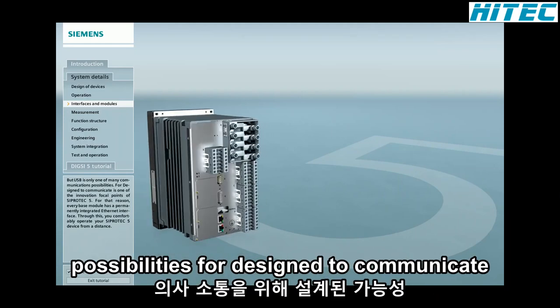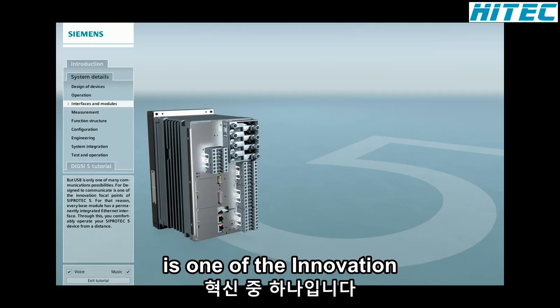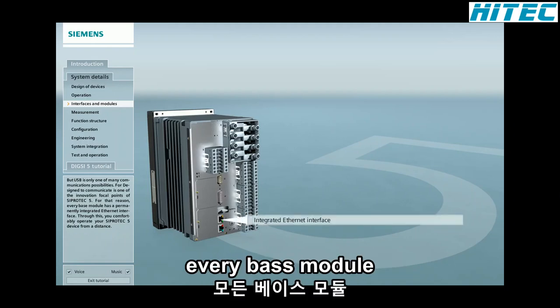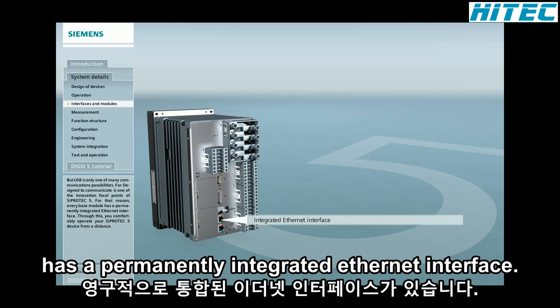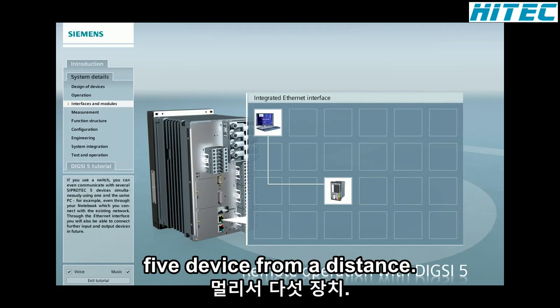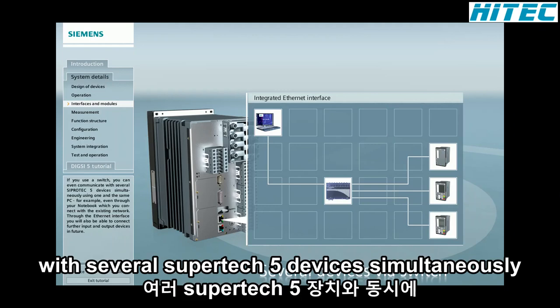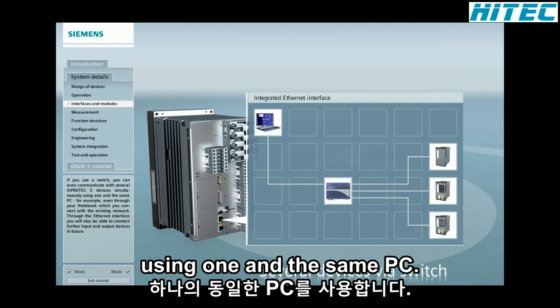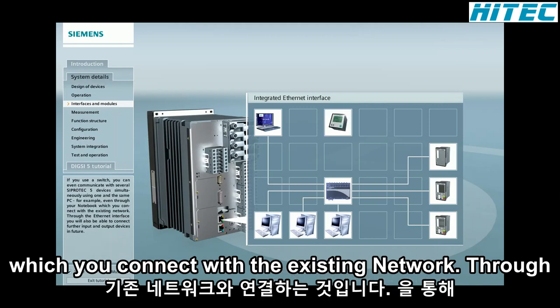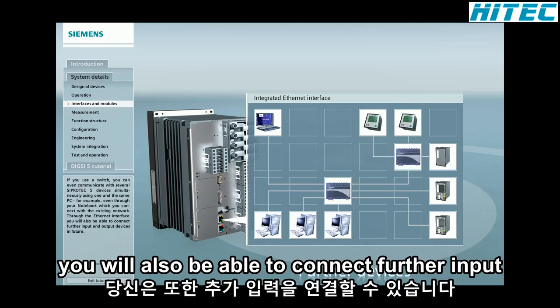But USB is only one of many communications possibilities, for Designed to Communicate is one of the innovation focal points of SIPROTEC 5. For that reason, every base module has a permanently integrated Ethernet interface. Through this, you comfortably operate your SIPROTEC 5 device from a distance. If you use a switch, you can even communicate with several SIPROTEC 5 devices simultaneously using one and the same PC, for example, even through your notebook, which you connect with the existing network. Through the Ethernet interface, you will also be able to connect further input and output devices in future.